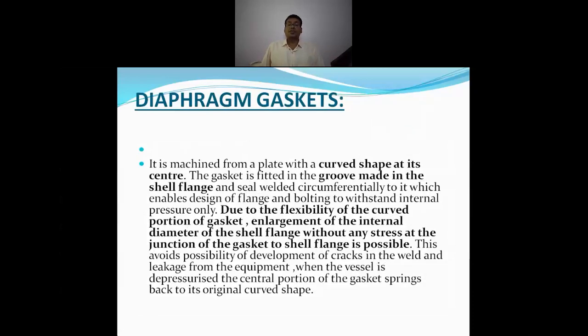Due to the flexibility of this curved portion of the gasket, enlargement of the internal diameter of the shell flange is possible without any stresses at the junction of the gasket and shell flanges. Generally, these are used in shell and tube heat exchangers, where floating heads are used.